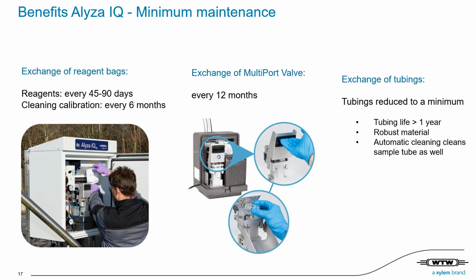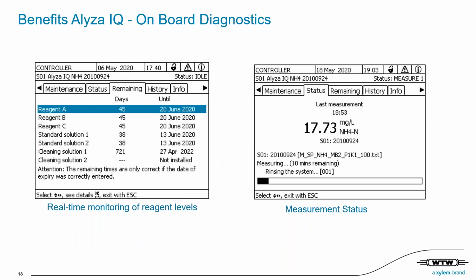So now let's dig into an additional benefit of the new Alyza. As a further enhancement, we have added predictive maintenance and onboard diagnostics. The Alyza IQ monitors the solution volumes and provides a countdown of the days remaining until you run out of solution and you need to replace it. The solution monitoring is individual to the solution type, so you have a counter for each reagent, calibration solution, and cleaning solution. So you really get a complete picture of how many days of operation are left. No risk of running out of chemicals anymore.